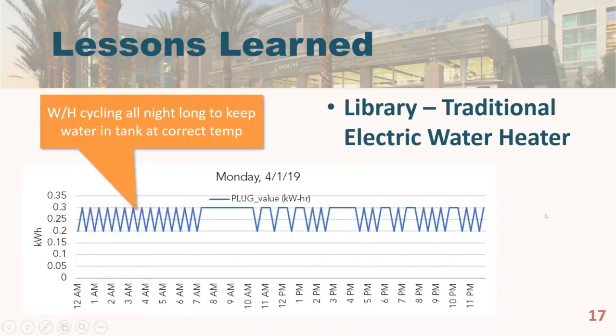This next one's interesting — another library for the county. This particular building has a traditional electric water heater with a tank, and the water heater is on their plug load panel. Once we started reviewing the data, we noticed something was cycling on and off all night long. It turned out the water heater was always trying to keep the water at a specific temperature, and even when we tried to put it in eco mode, it would only reduce the temperature by about 20 degrees.